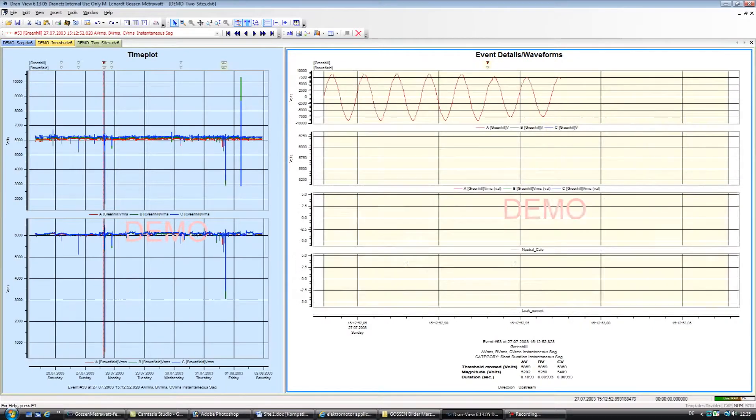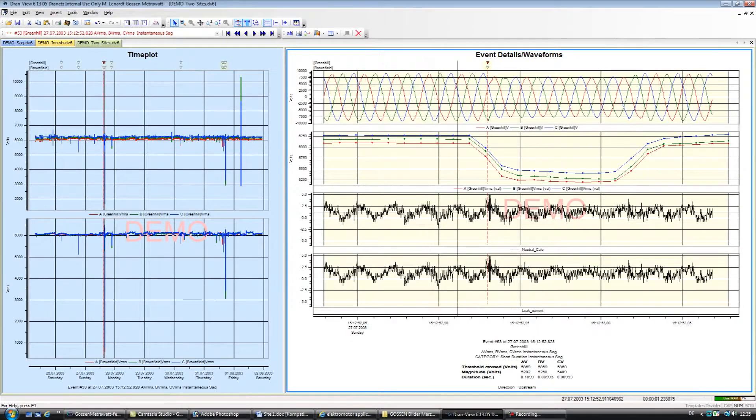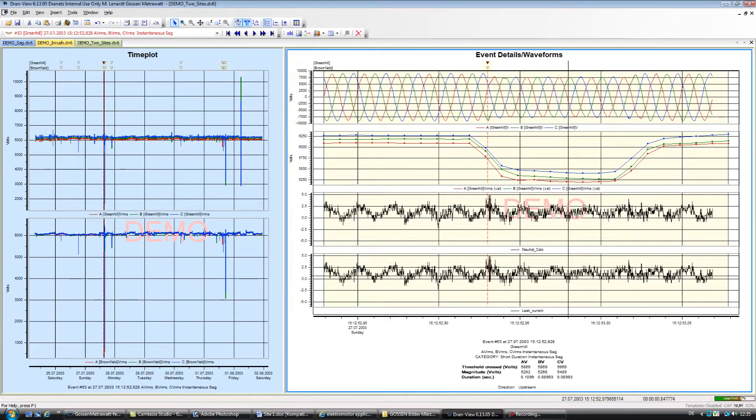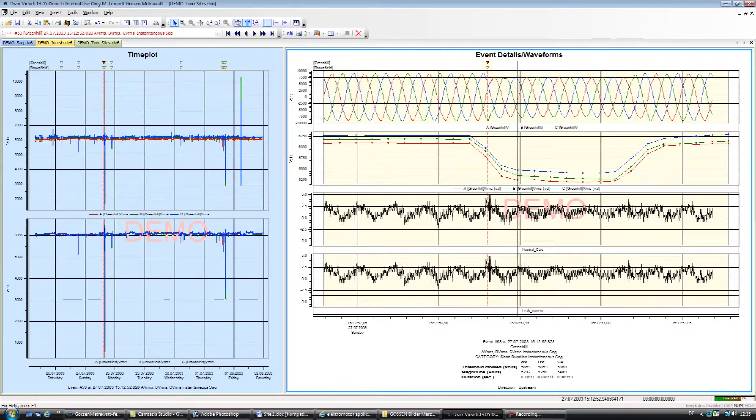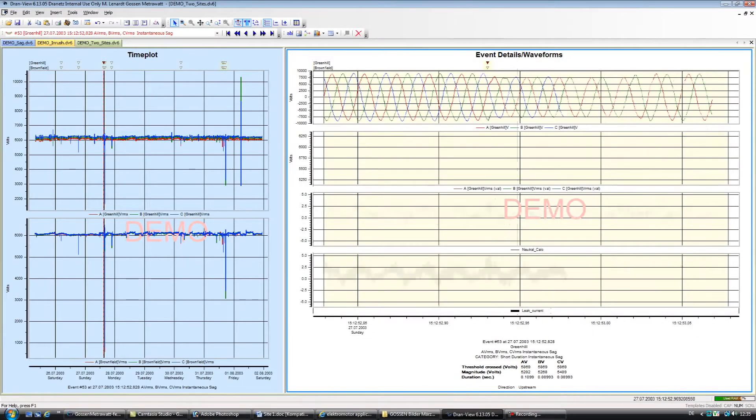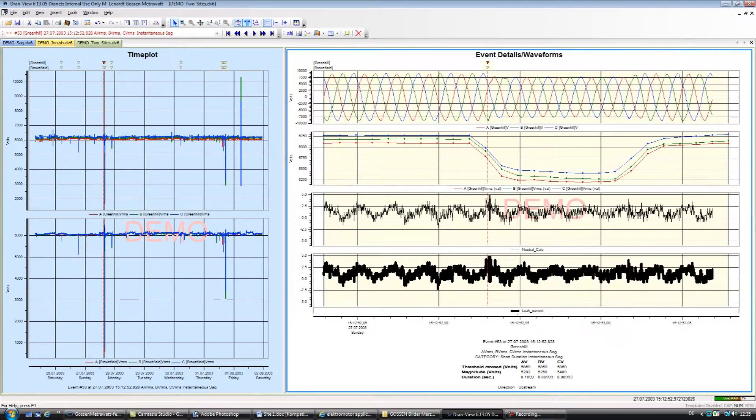A common application is to compute ground leakage current in a three-phase Y circuit. In such cases, the current in phases A, B, C, and neutral are measured by the power monitor. Using Dran-View, you can create a math channel to compute leakage current by adding the current in phases A, B, C, and neutral, with the remaining current being leakage current.